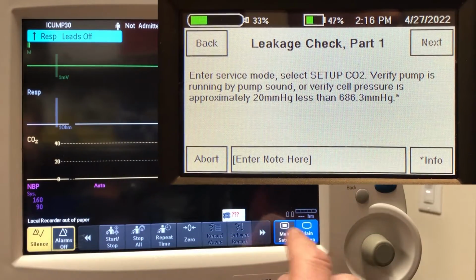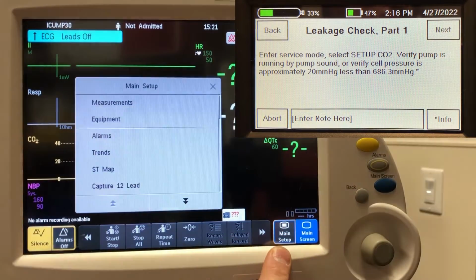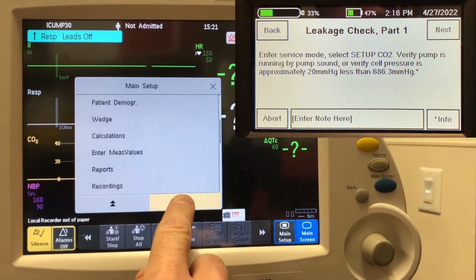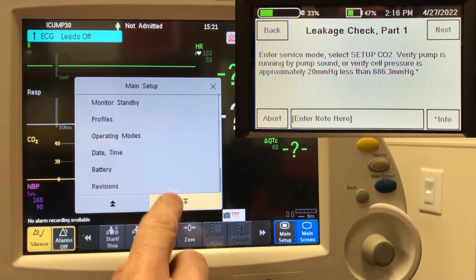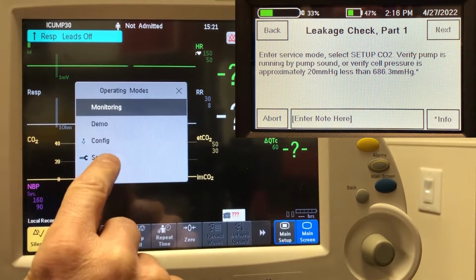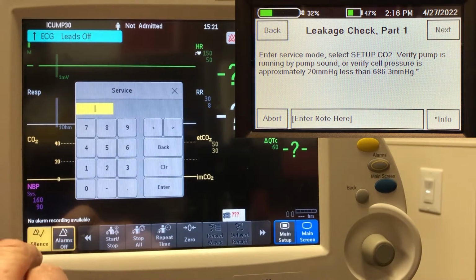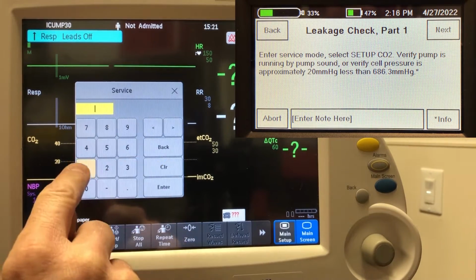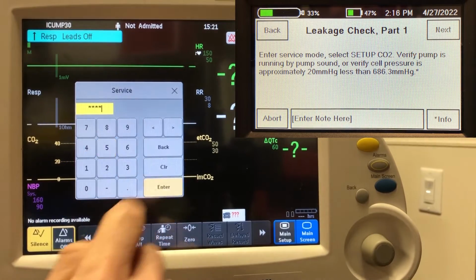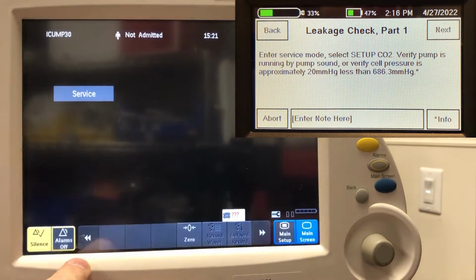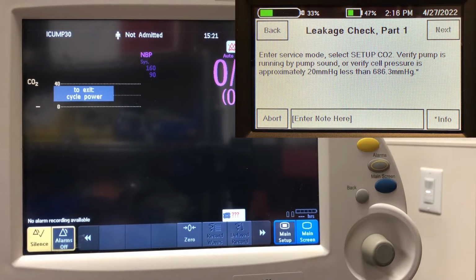So we're going to enter service mode by touching main setup. Then we're going to scroll all the way down to operating modes, and we're going to touch service. And then we've got to enter the passcode for this device. And now the monitor is in service mode.